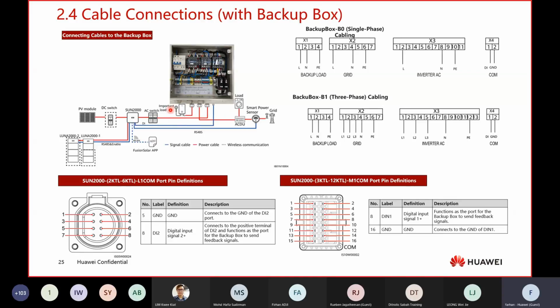Maybe during the day the AC will be lost. Only this load will have the power supply, not your normal load. So here you can see the cable connection for the single-phase or three-phase backup box. We have terminals X1, X2, X3, and X4. The backup load comes from the X1 terminal. X2 is from the grid, and X3 goes from the AC to the inverter side.